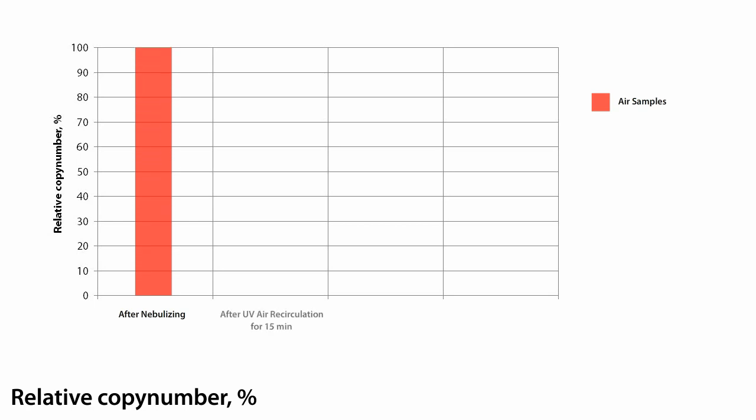For the first time shown, Biosense UV cabinets have 100% efficiency of inactivation of viral DNA and DNA amplicons in the cabinet set after the combined treatment of UV air circulation and open UV lamp irradiation for 15 minutes.